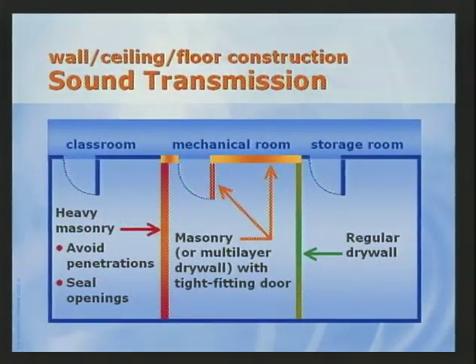Let's look at the structural transmission path first. The advantage of path attenuation on central systems cannot be realized unless the unit is properly located. Construct the walls, floor, or ceiling surfaces that are common to sound-sensitive areas out of materials with the proper transmission loss. This can sometimes be difficult with roof-mounted equipment. The best location for large rooftop units and central air handlers is away from sound-sensitive spaces. Place the unit over or surround it with non-sound sensitive areas such as bathrooms, utility rooms, and stairwells.